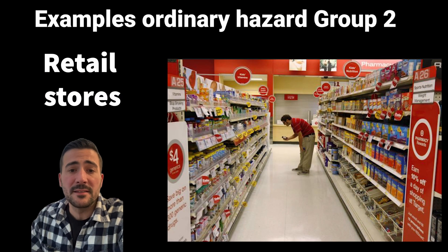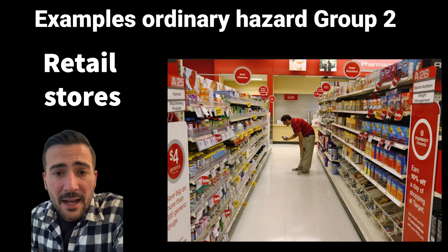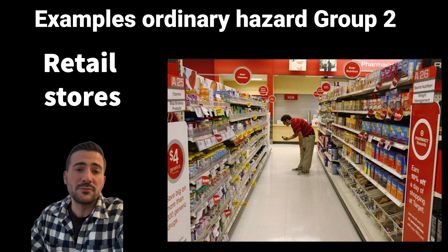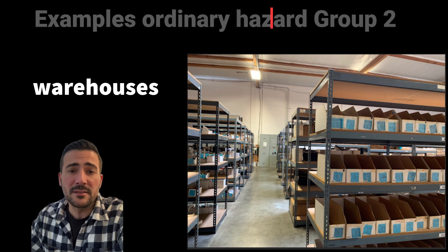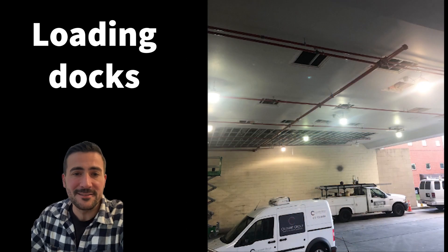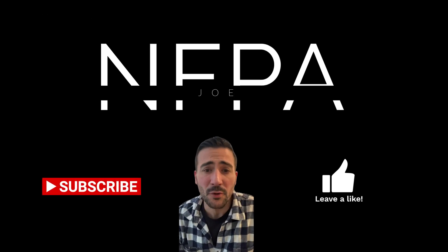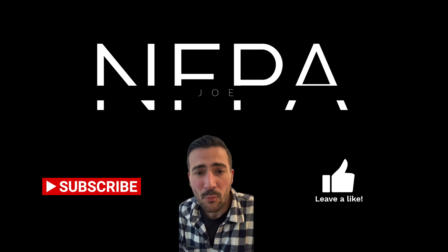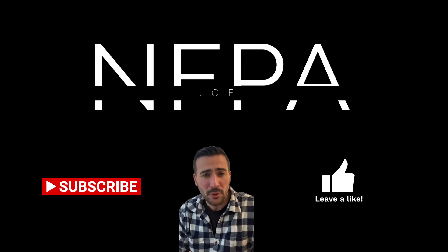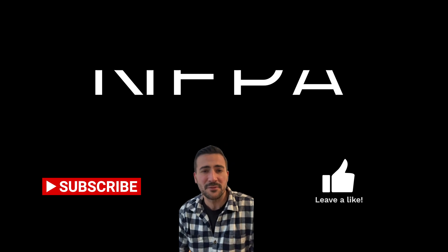Some examples of ordinary hazard Group 2 include retail stores, warehouses, and loading docks. Storage stockpiles of contents with moderate rates of heat release do not exceed 12 feet; if contents have a high heat release, storage will max out at eight feet. That covers ordinary hazard Group 1 and 2.